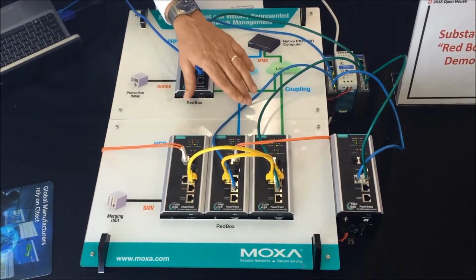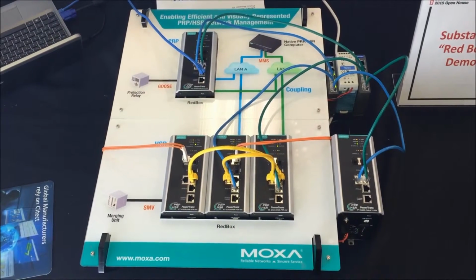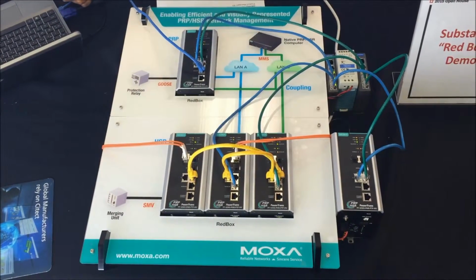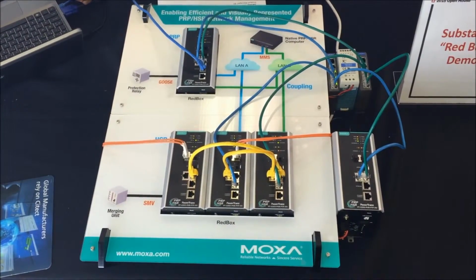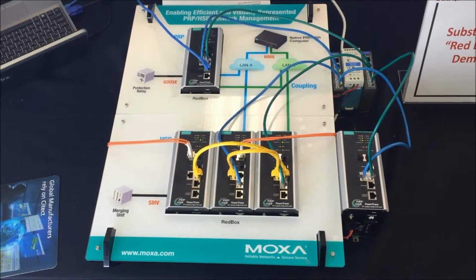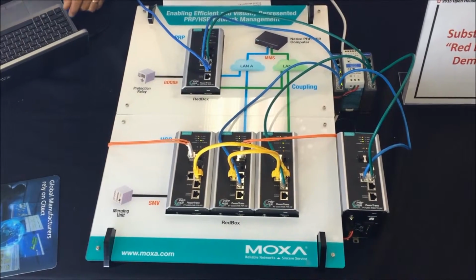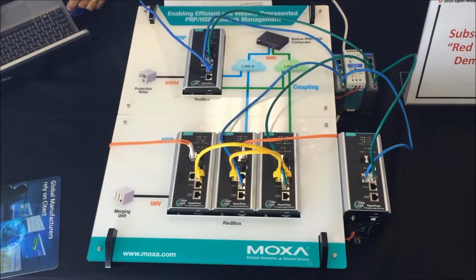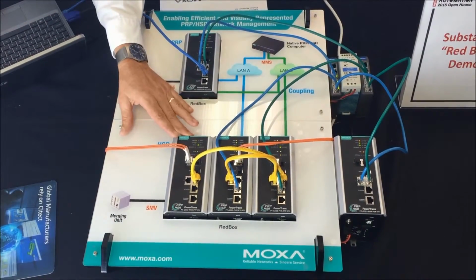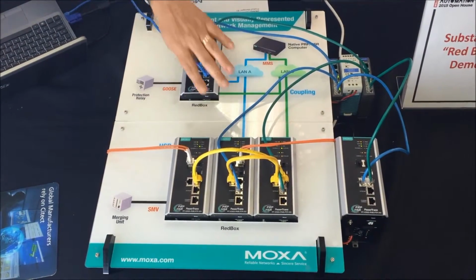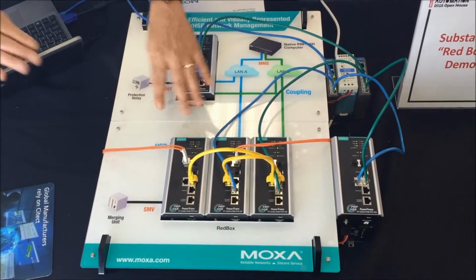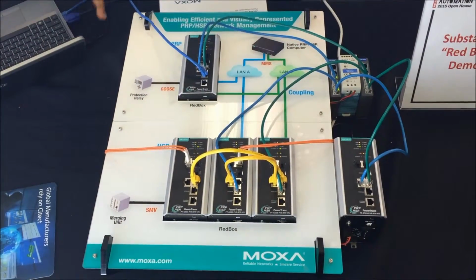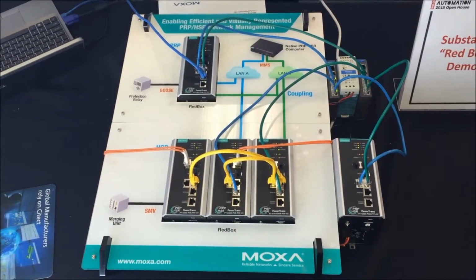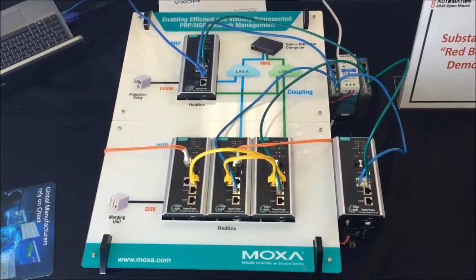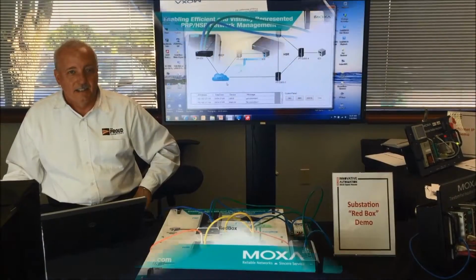When it's received on the other end, the firmware drops one of them and delivers one to the device on the other side. Because it's sent in parallel, there is no failover like there is in a typical ring topology. Now the ring topology is the same way. The frame is sent both ways out of the switch, so there is no loss if there's a break, and there's no time for reconvergence because the network's already converged.